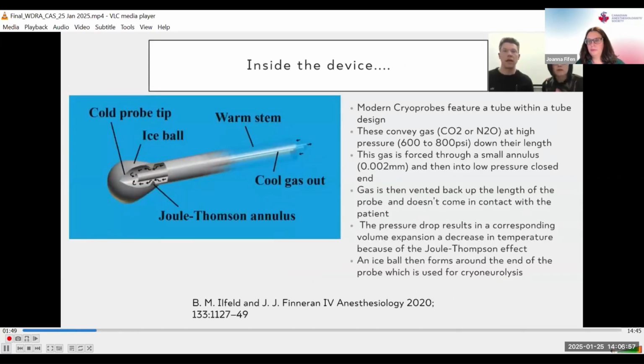You may wonder how the device actually works. Well, most modern cryoprobes feature a tube within a tube design. They convey high pressure gas, usually carbon dioxide or nitrous oxide, through the outer tube down to a narrow annulus, which then empties into a low pressure closed end. This then causes a cooling effect based on the Joule-Thomson effect, resulting in ice ball formation from the patient's water in their own tissues. The gas is then vented through the inner tube and back out the cryoneurolysis device.